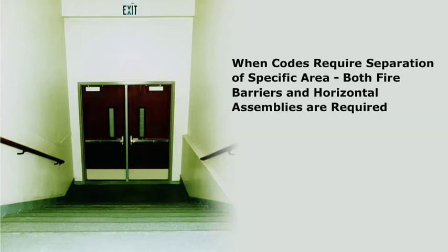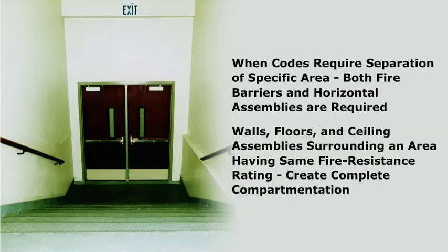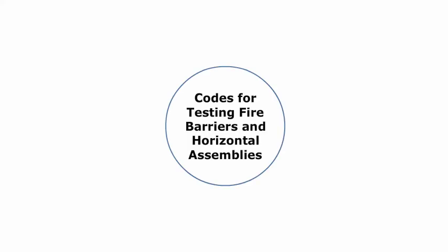In most cases when the codes require the separation of a specific area, both fire barriers and horizontal assemblies are required. When the walls, floors, and ceiling assemblies surrounding an area have the same fire resistance rating, it creates a complete compartmentation both vertically and horizontally — like a four-sided box with a top and bottom. An example would be the enclosure of an exit stairway where all four walls, the floor, and the ceiling or roof have a two-hour rating.